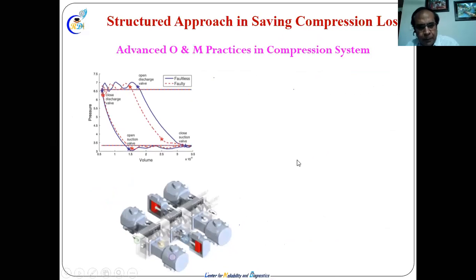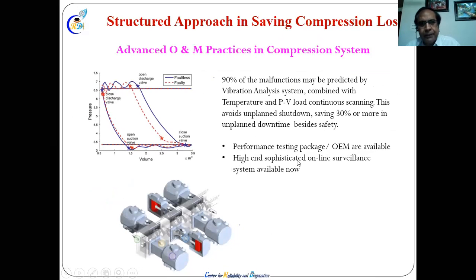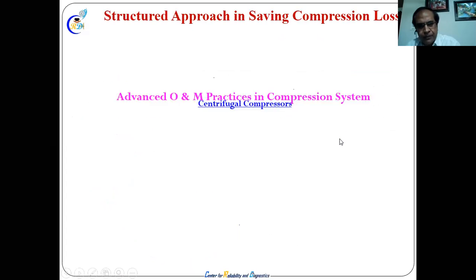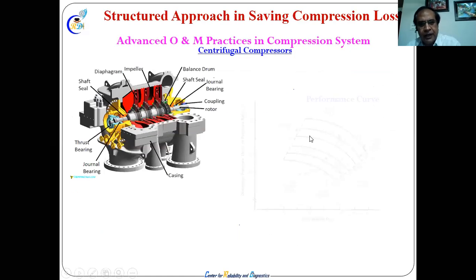So in the system approach, again PV diagram and failures and faults, we have to maintain this, and we can get the analysis done by an external agency, or people are there who can do this PV diagram, and we can find out whether it is compression or suction, or if there are problems in the PV curve. Accordingly, we can act.